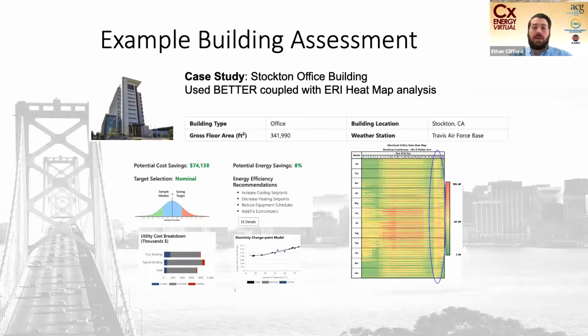Some of their cooling and heating set points needed adjusting because they hadn't installed window filming in certain areas of the building, resulting in excess heat loads. After addressing that, they solved the problem. Also, the economizers on the south side of the building were sometimes stuck open or stuck closed, depending on what they were doing, due to a programming or sensor location issue.